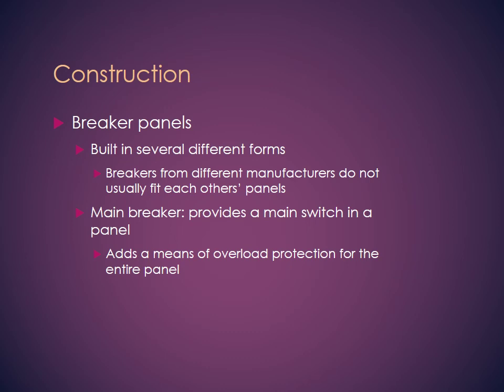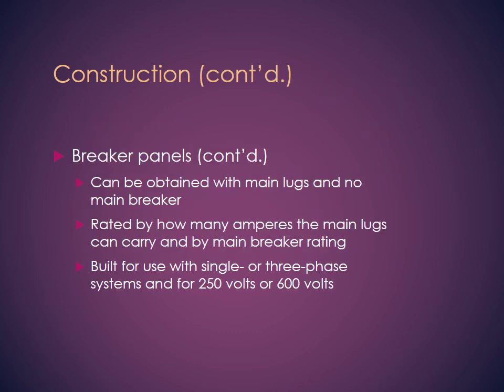Again, note this. They are not all uniform. Every manufacturer and every control panel has its own connections, and they have their own breakers that are designed to work with that panel. So make sure they are uniform, and they all have to be UL approved, which is Underwriters Laboratories approval, which goes under the NEC code. Construction. Main lugs, that's where you connect to. It's called a lug. Those are the connections, and they are rated again by amps.